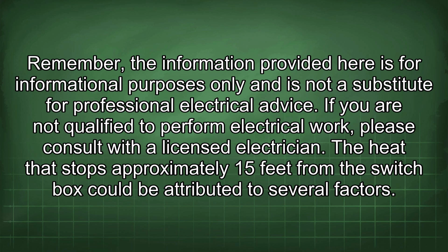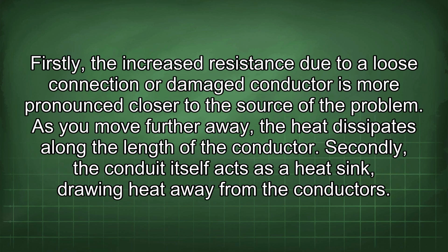If you are not qualified to perform electrical work, please consult with a licensed electrician. The heat that stops approximately 15 feet from the switch box could be attributed to several factors. Firstly, the increased resistance due to a loose connection or damaged conductor is more pronounced closer to the source of the problem. As you move further away, the heat dissipates along the length of the conductor.